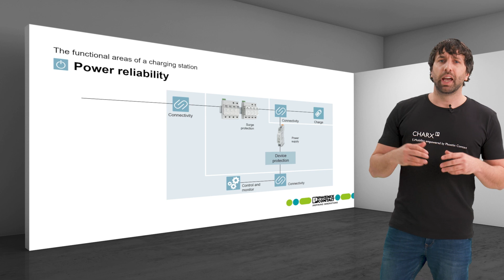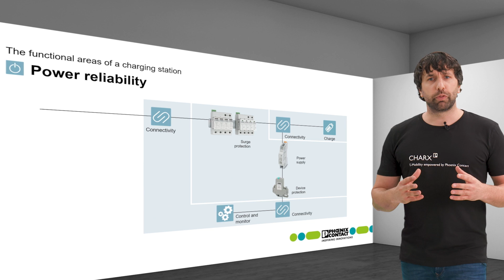In charging stations, additional components and higher loads are added, which increases the need for a device protection. A thermomagnetic device circuit breaker is the optimal solution here, as it can be easily reset after tripping. Therefore, it supports a high availability of the charging point.